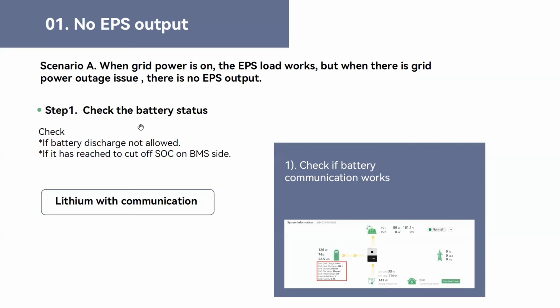Step 1. Check the battery status. Check if the battery discharge is not allowed, if it reached the cutoff SOC on the BMS side. This is with lithium with communication. On the web monitoring, check if the battery communication works. This is where you check the BMS status.